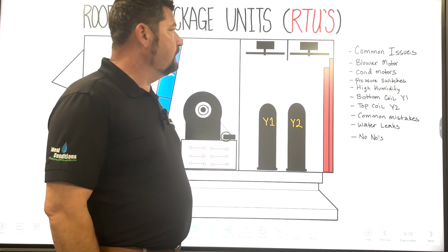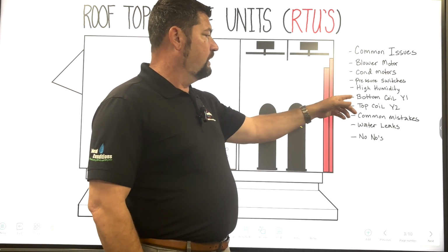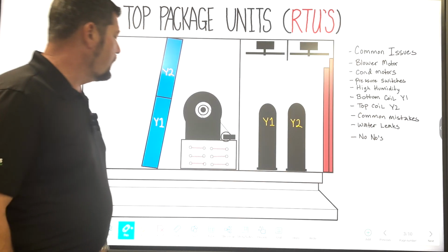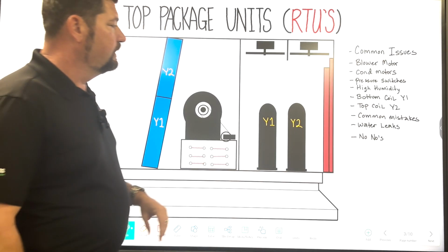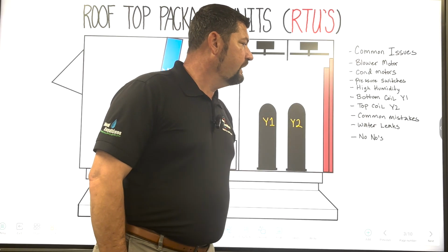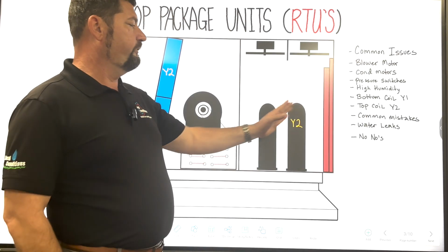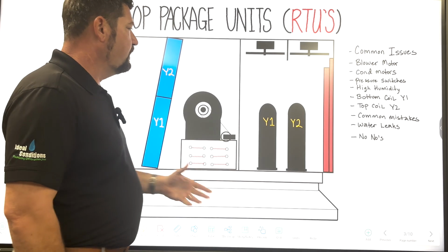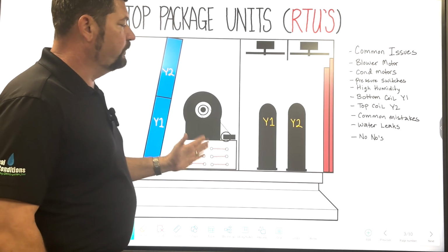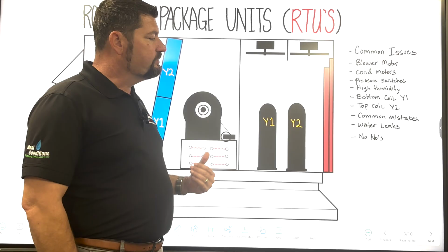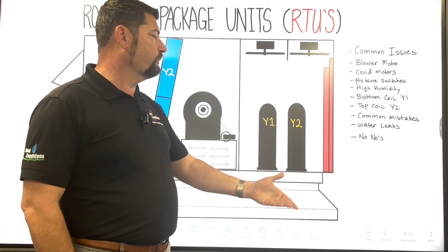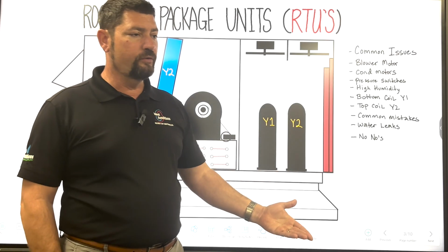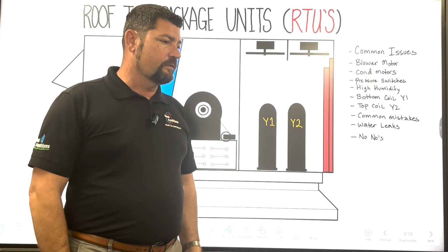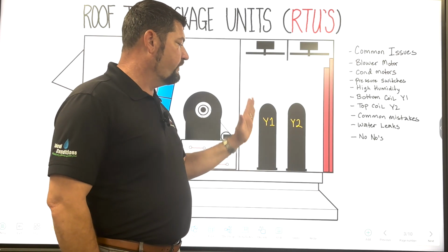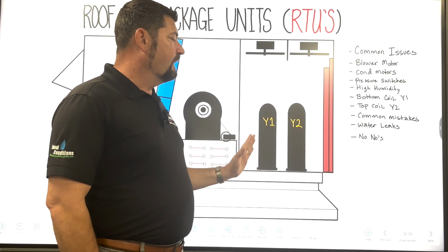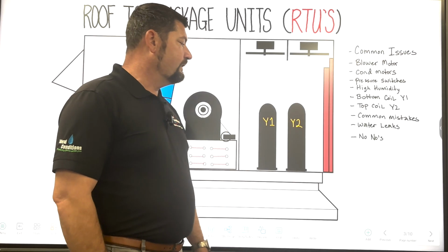There's always a high humidity concern. We're going to go over that in a little bit. The bottom coil and the top coil, that's your Y1 and Y2. We're going to cover that. Going into the common mistakes, a lot of people don't understand their refrigerant circuits. When we talk about Y1 and Y2, we're talking about circuit 1 and circuit 2. Sometimes these are labeled A or B, or 1 and 2. Sometimes your compressors are different sizes, so you might have a higher BTU on Y1 and a lower BTU on Y2.